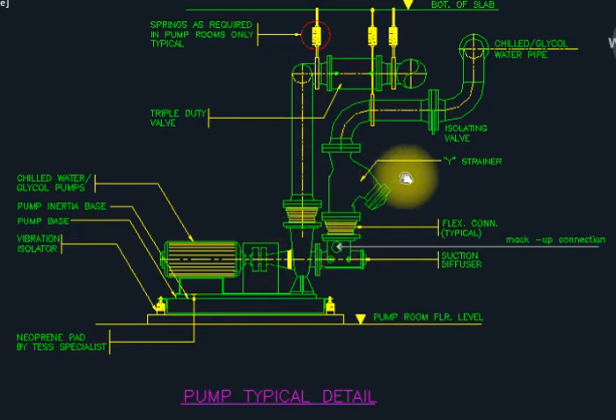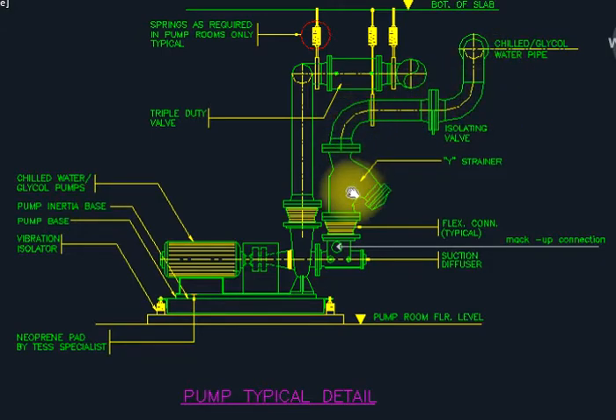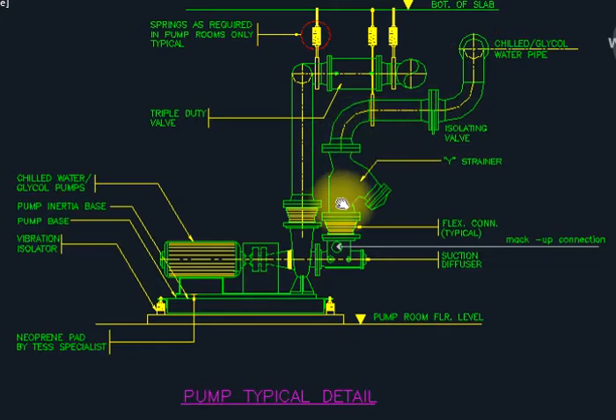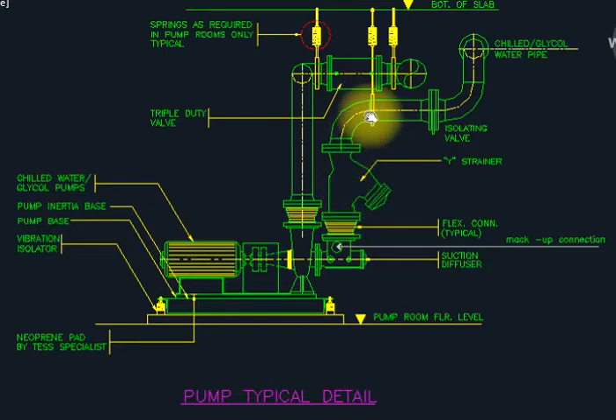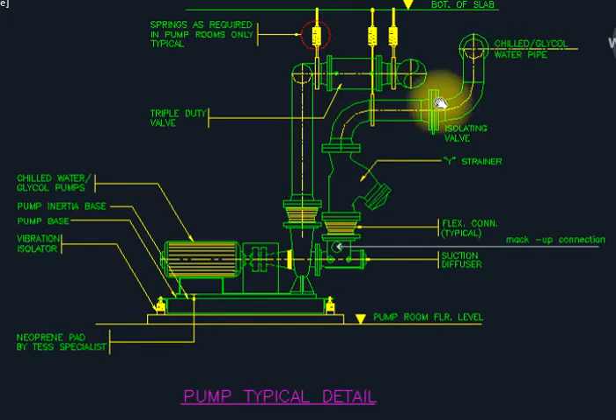This is the suction line and this is the discharge line. Whenever we have the suction line, we provide Y-strainers. When you see a strainer installed in the pipe, it means it is on the suction side; if there is no strainer, it is the discharge side. Any garbage collected in the strainer we open and clean. Here we also have isolating valves — simple gate valves — and the chilled water pipe goes to the chilled water header.